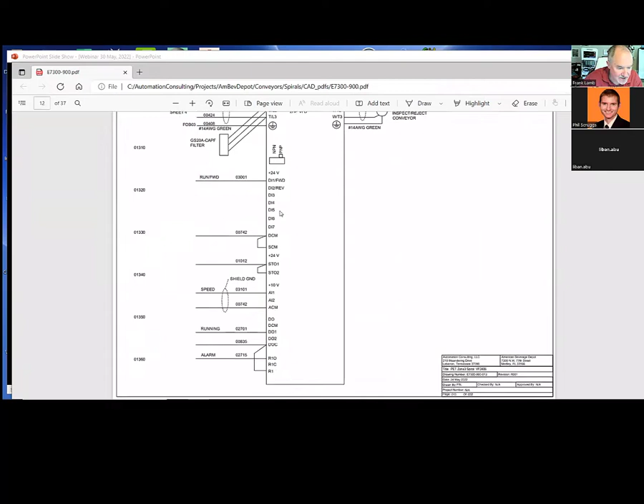When I got to the third one, the case turner, it was a completely different drive with a different layout. I had to look up online to find the pinout for this particular drive. It's a Lenze 1.5 horsepower VFD, and that's even a guess. I couldn't find the horsepower on the drive itself, someone said it was 1.25, but there was no 1.25 in the list I found online. These others are 2 horsepower, brand new Durapulse drives from Automation Direct.